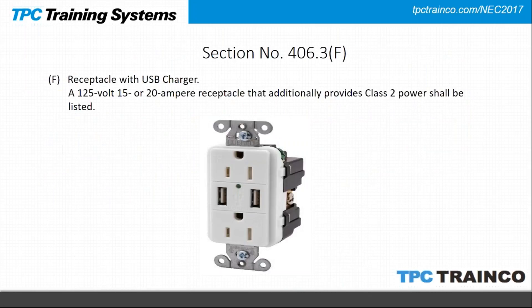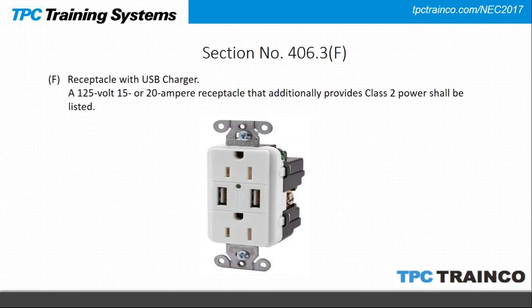The last change is in Article 406 under receptacles: receptacles with USB chargers must now be listed by a recognized listing agency. These receptacles have been available for a while, but chargers were being added to existing receptacles in ways that weren't ideal for charging electronic equipment. Going forward, all USB receptacles must be UL listed; if they are not listed, they are not legal to install. With that, I'll turn it back over to Eric to wrap up.